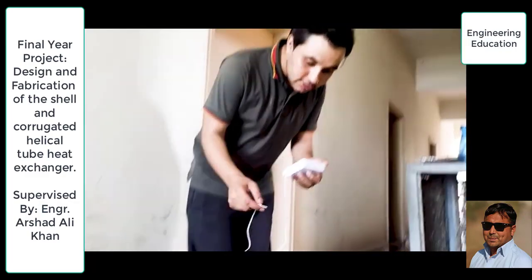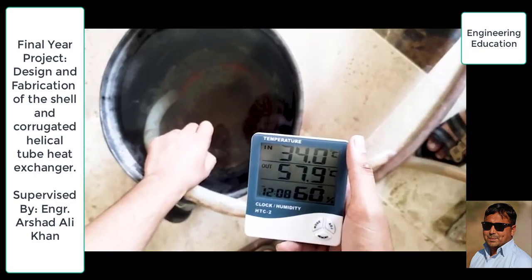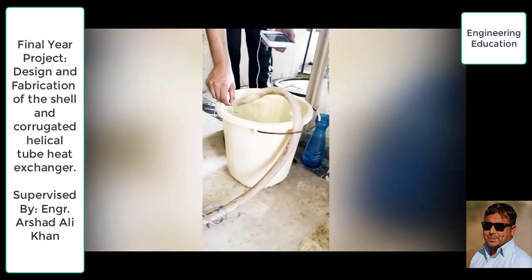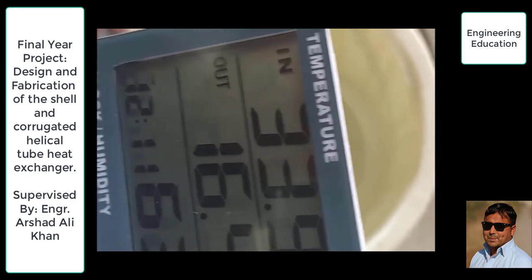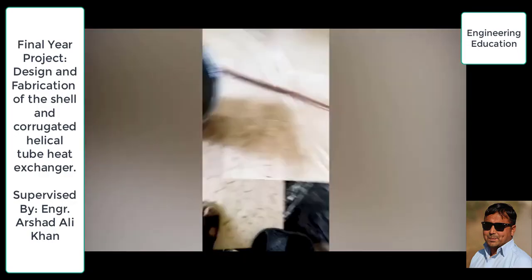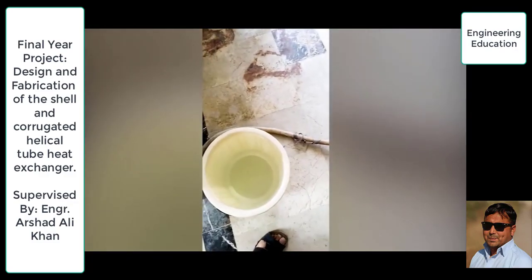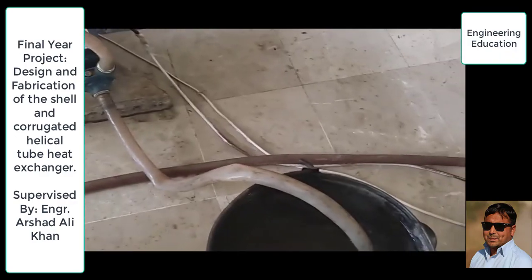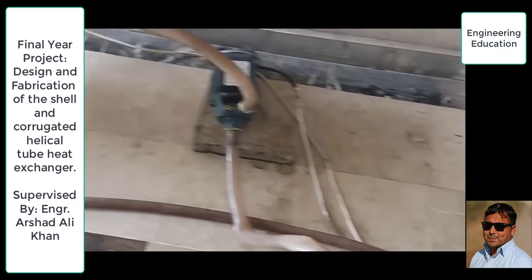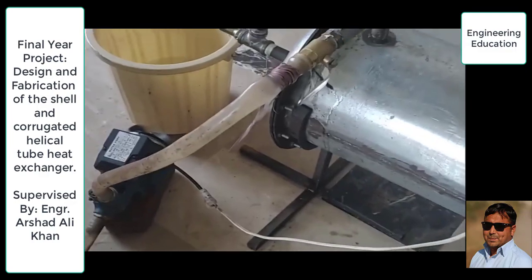We are going to take the temperature at the inlet and outlet. The hot water inlet temperature is 57.9 degrees centigrade, and the inlet temperature of the cold fluid is 16.4 degrees centigrade. Now turning on the pumps — the pumps are working. This is the hot fluid and here we have the cold fluid. Now we are going to find the temperatures at the outlet of the tube and shell.